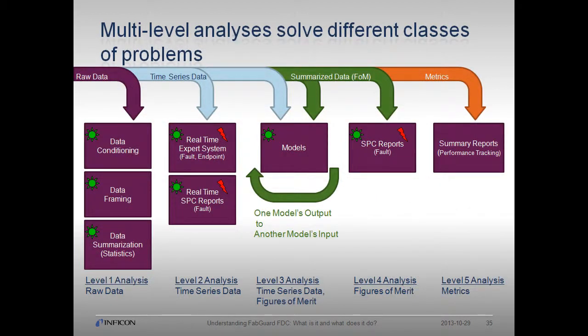FabGuard performs analyses at multiple levels and timescales to detect as many different types of faults as possible. The first level conditions, frames, or summarizes raw data streams. Once conditioned, data is sent to level 2 analyses — FabGuard's real-time expert system or real-time SPC reporting. Summarized data are referred to as figures of merit, or FOMs. Both conditioned time series data and summarized data can be sent to level 3 analyses executed run-by-run, and these level 3 models can be chained together so the output of one model feeds the input of another. At level 4, only figures of merit are used for SPC reports. Finally, at level 5, metrics calculated from FOMs are used for summary reporting and performance tracking.